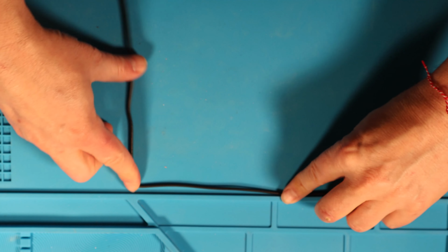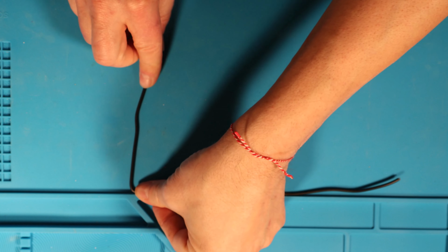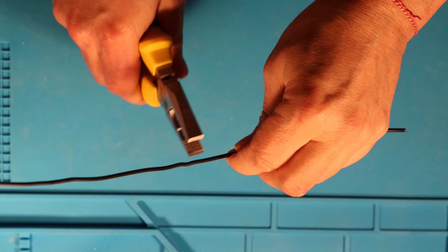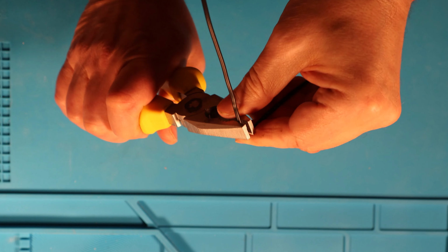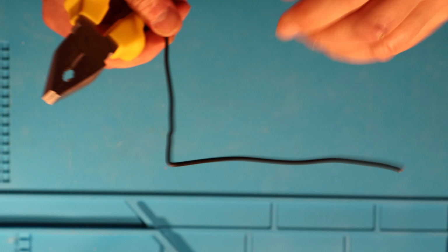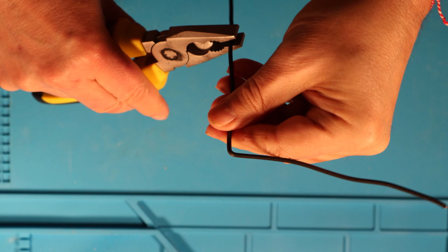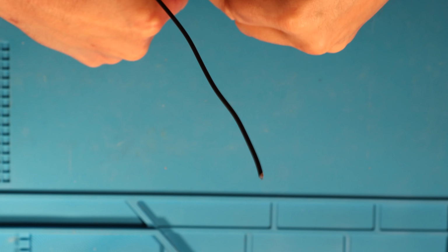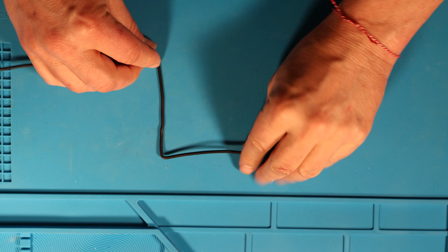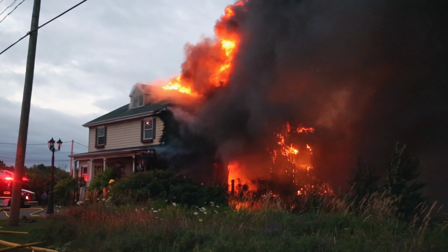There are plenty of people that don't know about these requirements. I've seen people doing this, for example, and this is extremely wrong. It looks great, but the structure is damaged, and that could result in heavy damage in the entire electrical system. With time, any cable suffers wear and tear. With the additional tension that the short radius creates in the material, that time is reduced significantly and could cause fire and short circuit in the electrical system, and could lead to this.